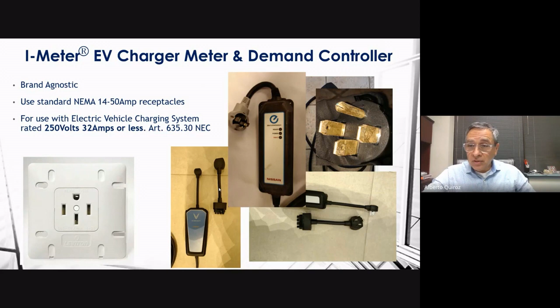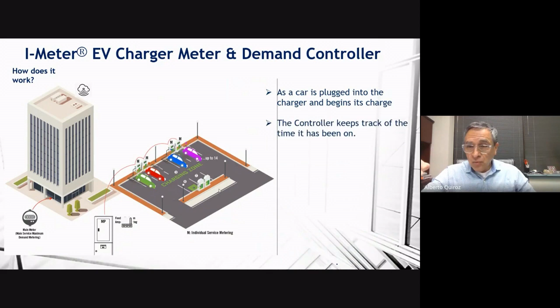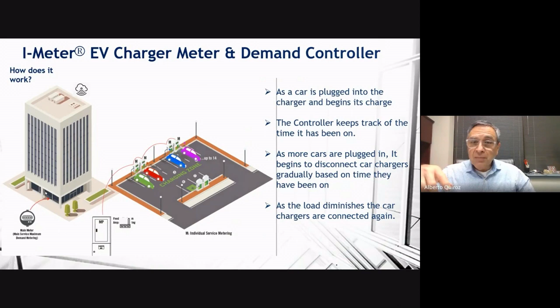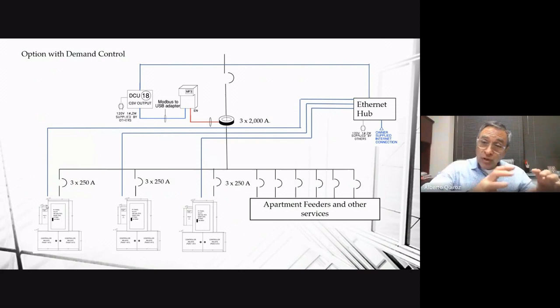As the cars come to charge into the building, we have the ability of tracking when they connect, when they start, and as the load increases, the EVCMC rotates that load. Picture this electric meter in the mains - we have the ability to look at what the building is consuming, so that when capacity is not being consumed by the building, whether it's the chillers, elevators, lighting, receptacles, or ventilation, when that's not working we can make it available for car charging. When the building uses it, we reduce the load of the electrical charging.